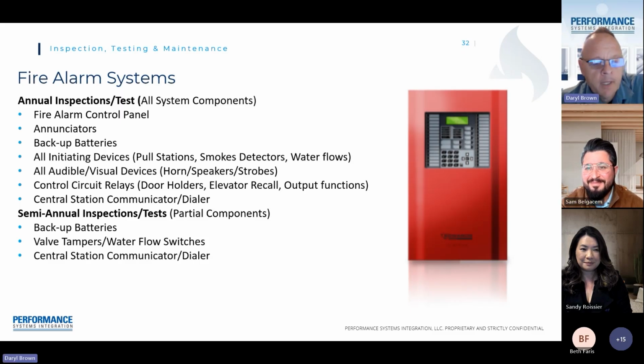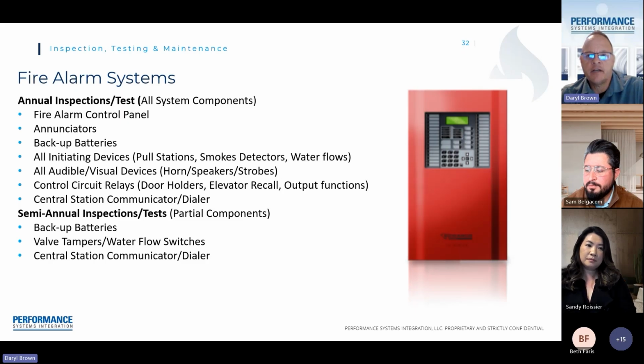Thank you, Sam. In summary, one thing to mention as we go through this: the requirements we have for fire alarm systems and the requirements we have for fire sprinkler systems. When we test and inspect, we're a consolidated vendor, so we're licensed by the state of California to do both fire alarm inspections and fire sprinkler inspections. When you test and inspect one, you're partially testing and inspecting the other.